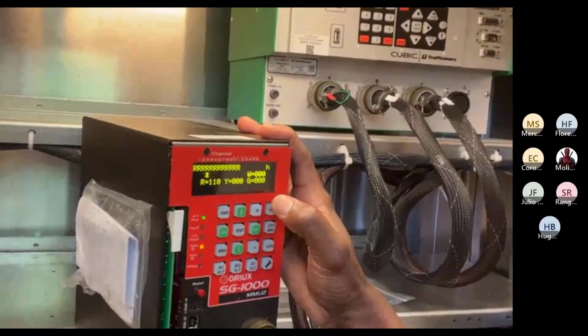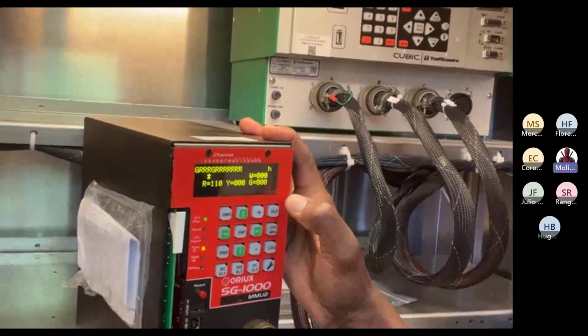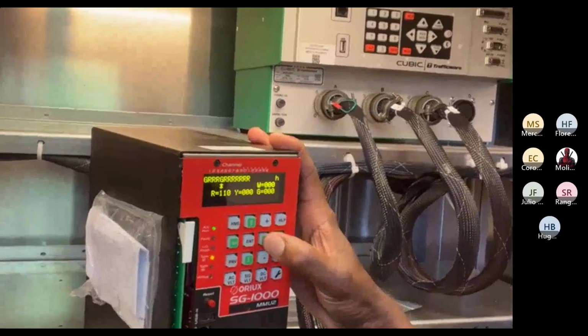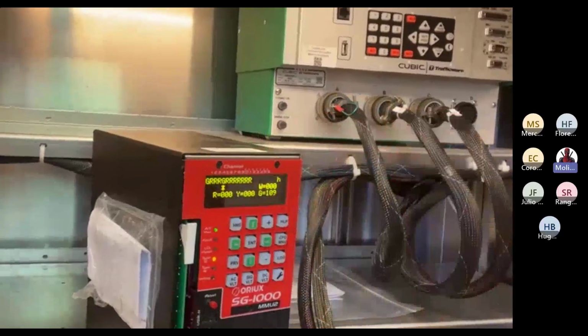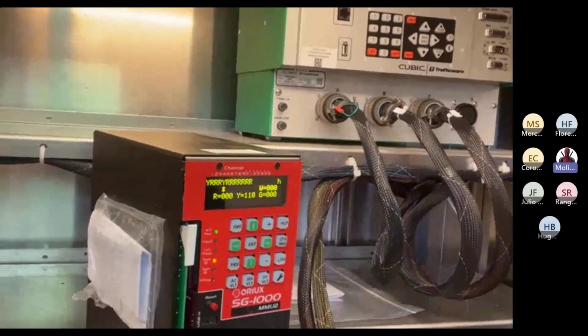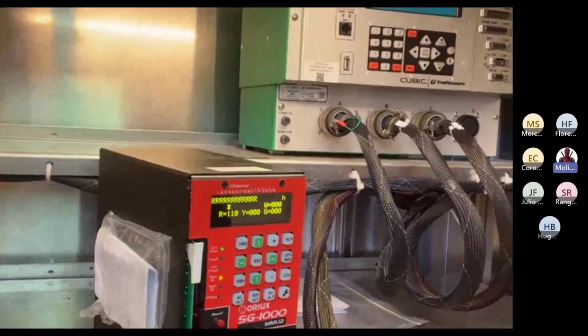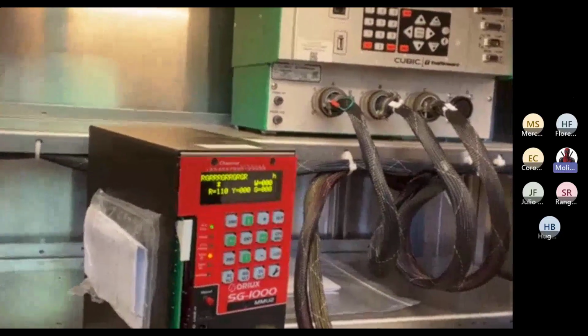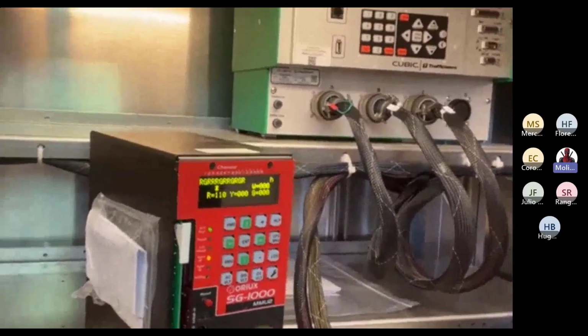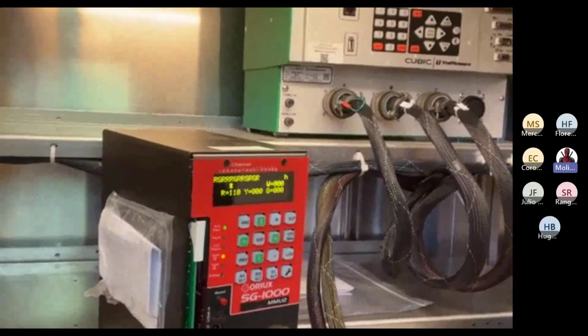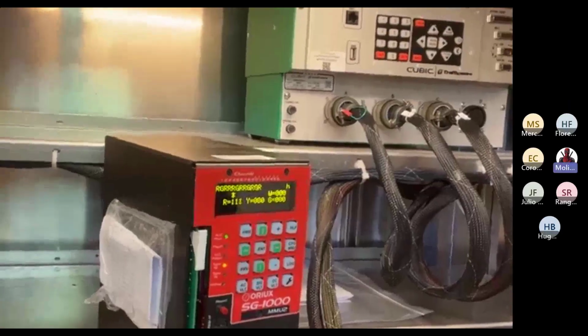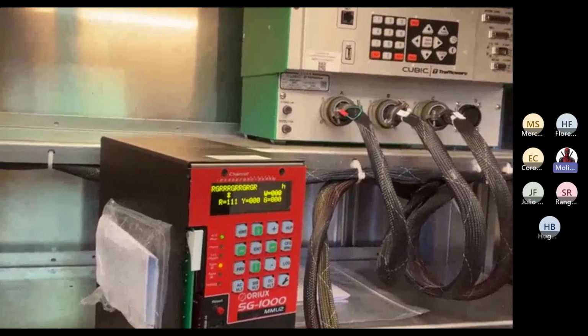Yeah, it'll also let me see. When the monitor faults, it will take a snapshot of all the outputs. And as long as you don't hit that reset button, you can cycle through all this and see what everything was at the moment that it faulted. So that's a good diagnostic tool to track down a problem.